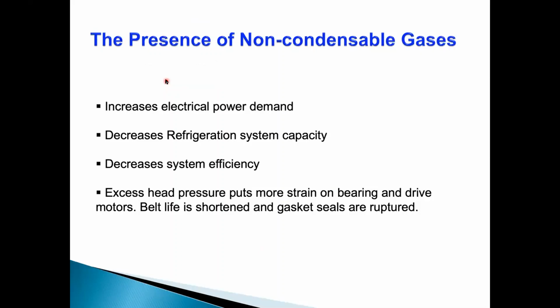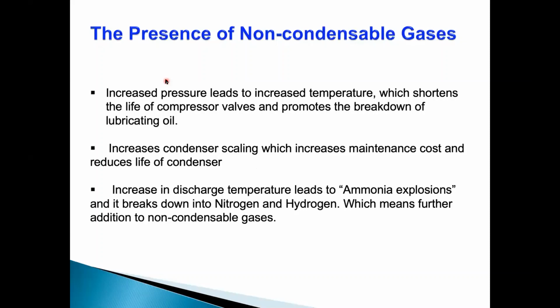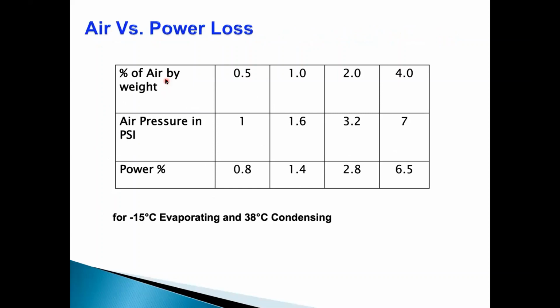It increases the power cost. As I told you, the pressure increases. It decreases the refrigerant efficiency. It affects the performance of your compressor bearings and compressor gaskets, and the compressor temperature rises. It can also lead to an ammonia explosion, breaking ammonia into nitrogen and hydrogen.